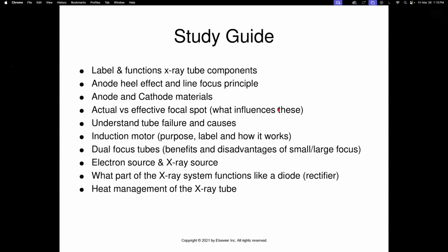I know it's tungsten and molybdenum. I think you're trying to say molybdenum. What I'm asking you is, what's the other property of tungsten that makes it a favorable material for the anode? High atomic number. Okay, why is that important? It's for efficiency. Very cool. I think you got it, Jacqueline.